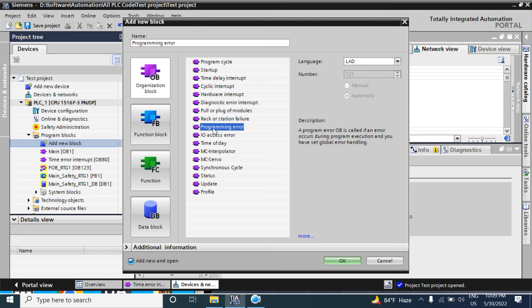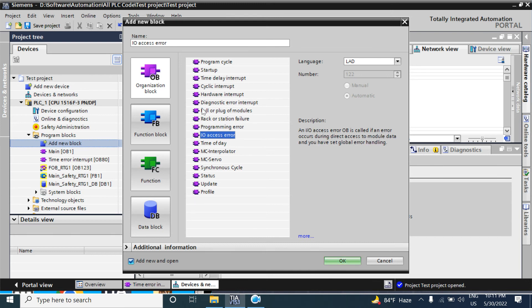The next OB is Programming Error. If any error happens — like array index out of bounds or BCD calculation errors in your program — the CPU will go to stop mode if you have not included this Programming Error OB in your user program. So you should add this block to handle programming errors.